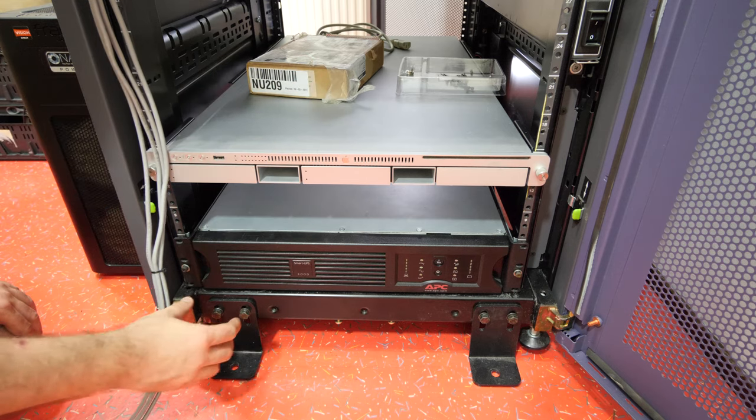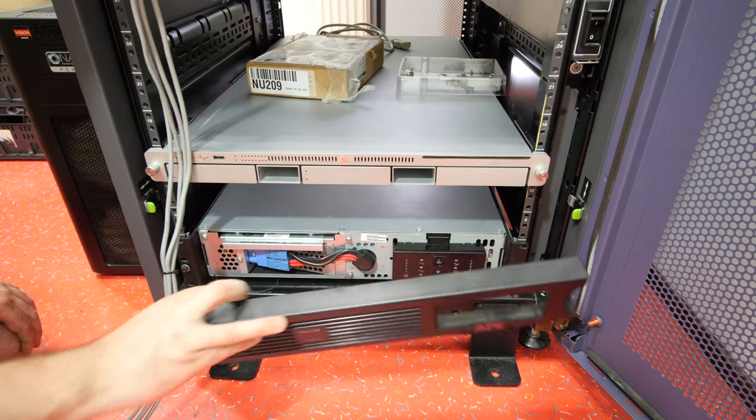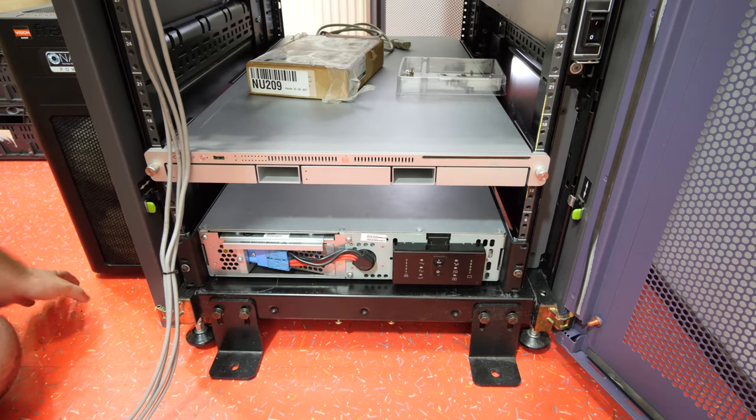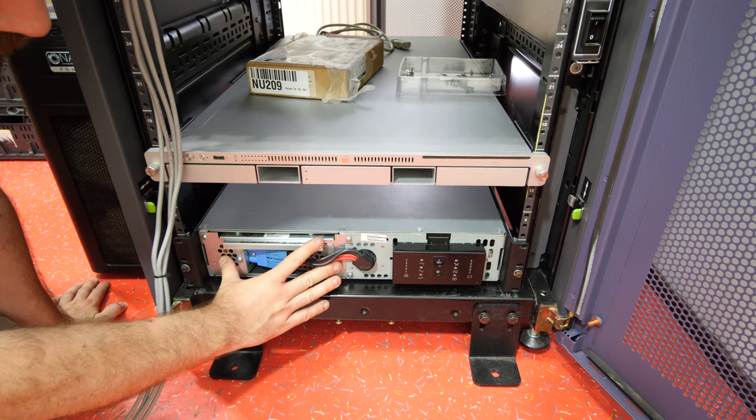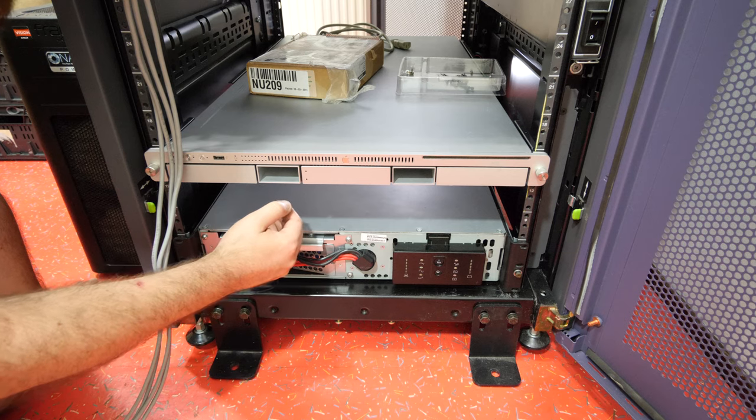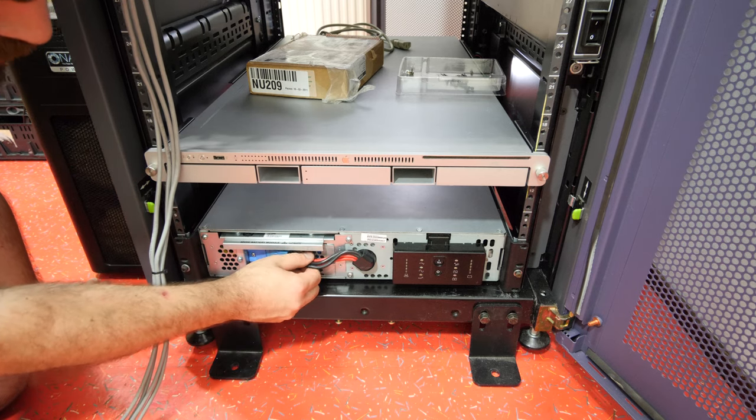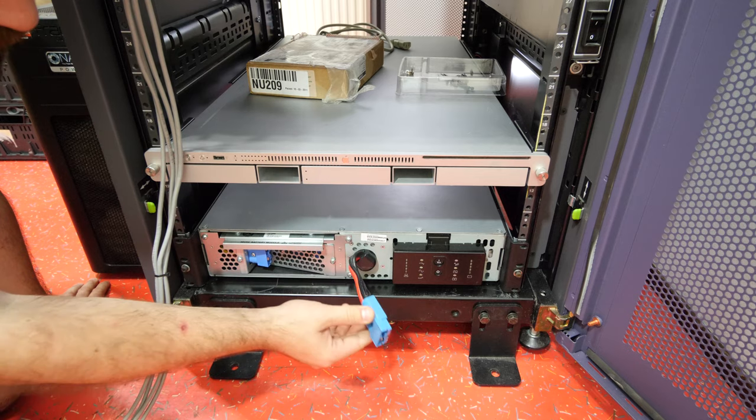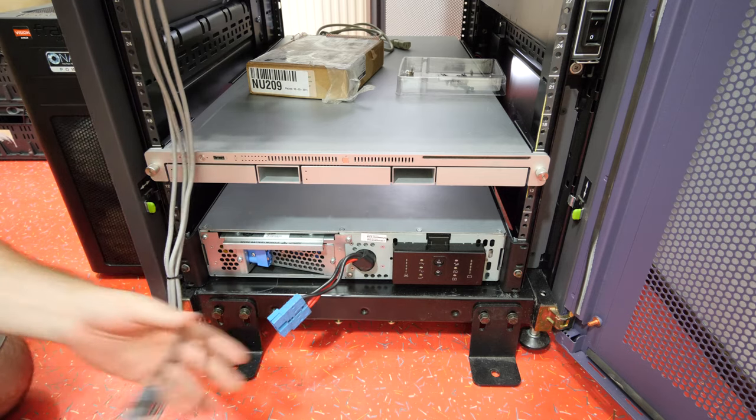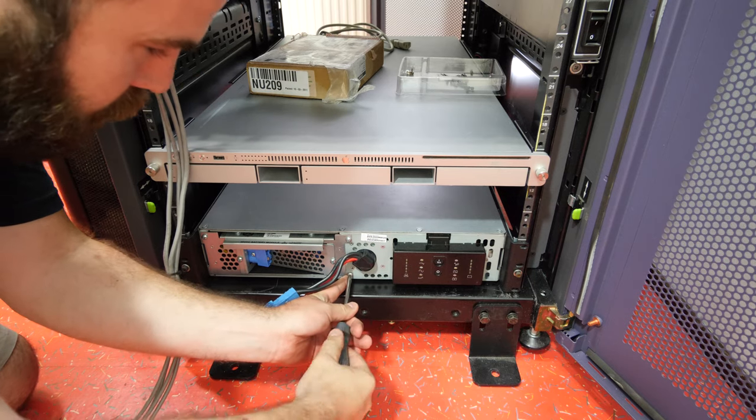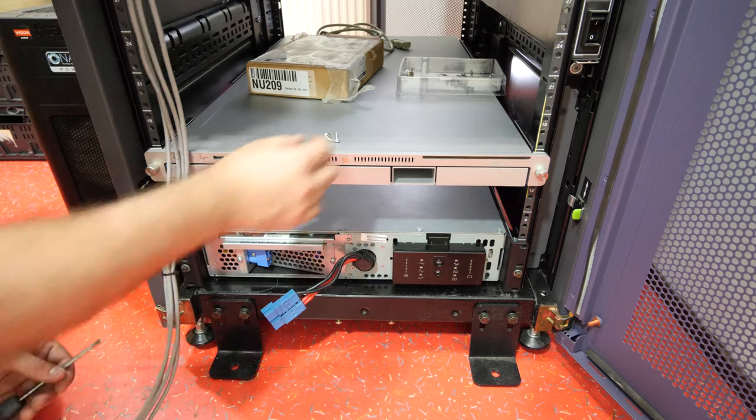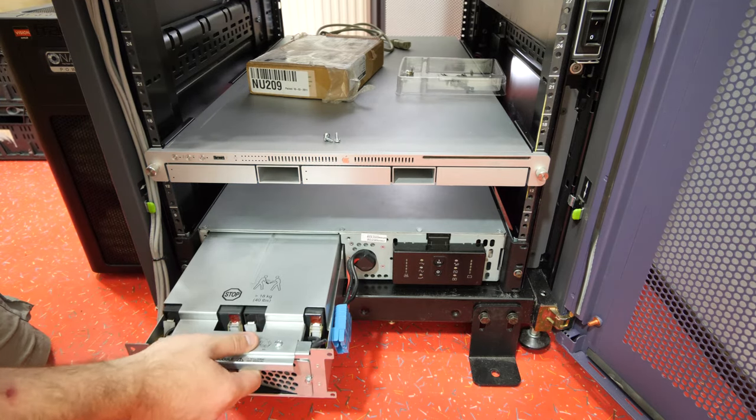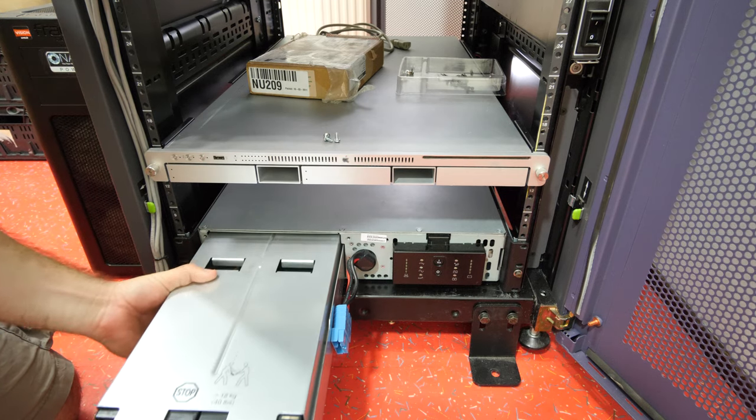Let's replace the batteries in this UPS. That is quite easy. When we remove the front panel we have here the battery pack, and we don't have to pull out the whole UPS out of the rack. Here's a really big connector to disconnect the batteries. With a screwdriver you can simply remove the unit. The battery pack is like 18 kilos, so be really careful when pulling it out.